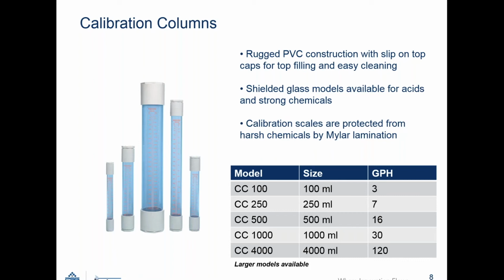Calibration columns are an easy way to measure the flow of your pump in the system. It's also a convenient way to troubleshoot your pump. When I say troubleshooting a pump, generally the flow will come down in straight shots down through the column, and seeing the actual flow coming down can tell you sometimes when a check valve is not holding properly and starts to bounce inside the cylinder. I always try to mention this just because it's not just a measuring tool. It's also a maintenance or troubleshooting tool used for pumps.